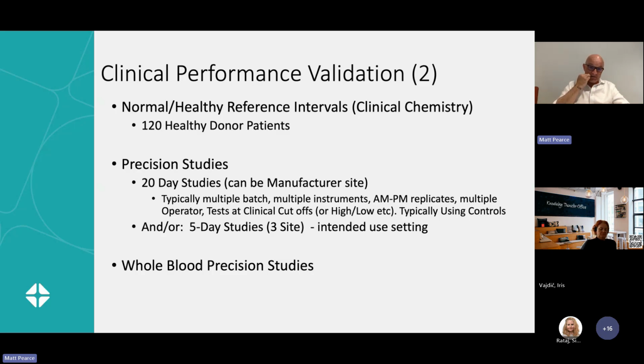As an alternative, the FDA will accept 3 5-day studies, but these need to be done in the intended use setting and not by the manufacturer. So those studies can be done as a bolt-on to the end of your clinical studies, for example, where they could run the 5-day studies. Both of these options have different merits. 20-day studies are difficult to do. They take a month, but they take a lot of effort, and they can go wrong very easily if you don't concentrate.